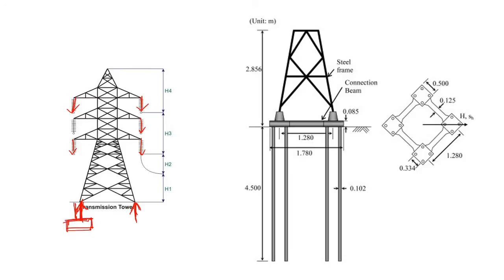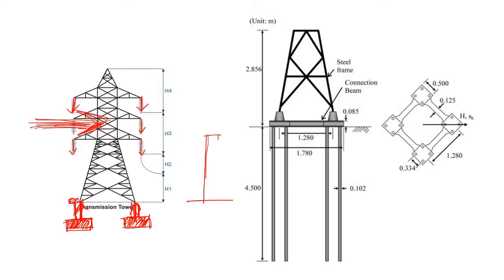Based on this compressive reaction you can either provide a pad foundation or, if you have low-quality soil or subgrade, you have to provide pile foundations. To carry this compressive force, a pad foundation or isolated foundation can be used. Now for lateral loads — let's say all the lateral loads are being applied at the center, giving a resultant lateral force. The tower can be modeled as a column fixed at the base with all lateral load applied at its tip.